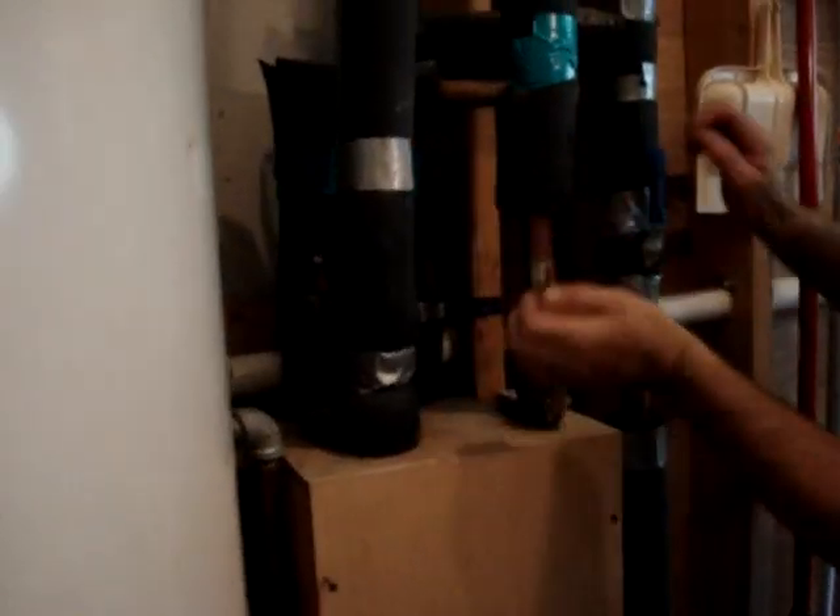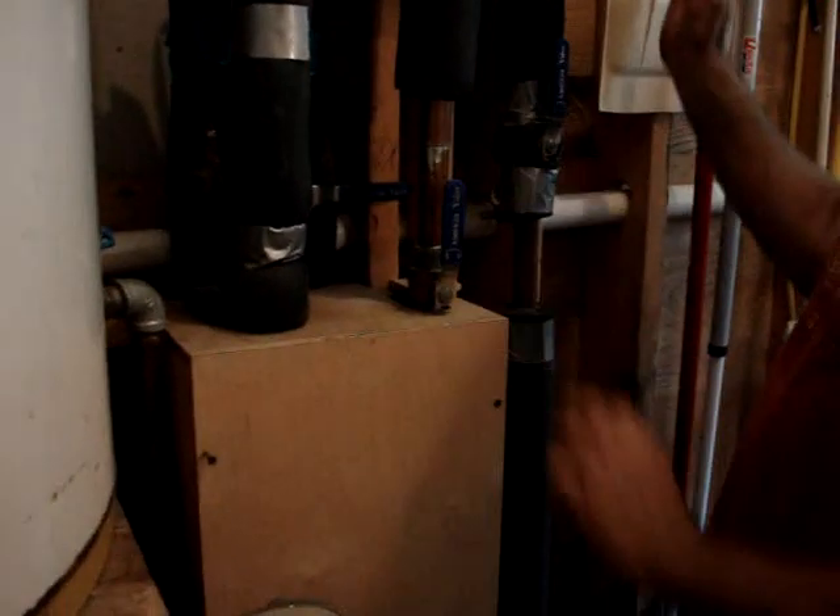During the winter, when I've got more hot water than I need — because I also heat with a wood heater — I turn these valves up and turn these off, and the water from those panels goes all the way through my concrete slab and warms the house and warms the slab.